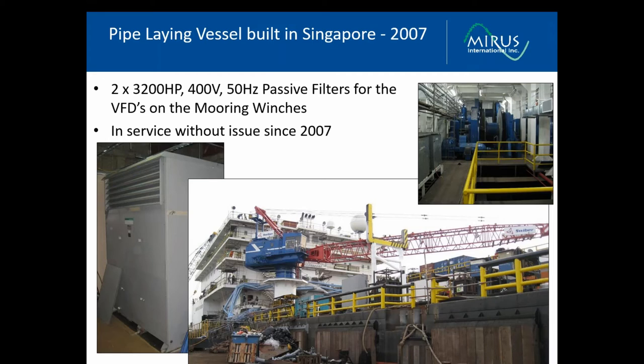And finally, this application was a pipe-laying vessel, and this was equipped with passive harmonic filters on the large VFDs of the mooring winches. It has been in service since 2007 without incident, and just recently brought into the shipyard in Singapore for service and maintenance.